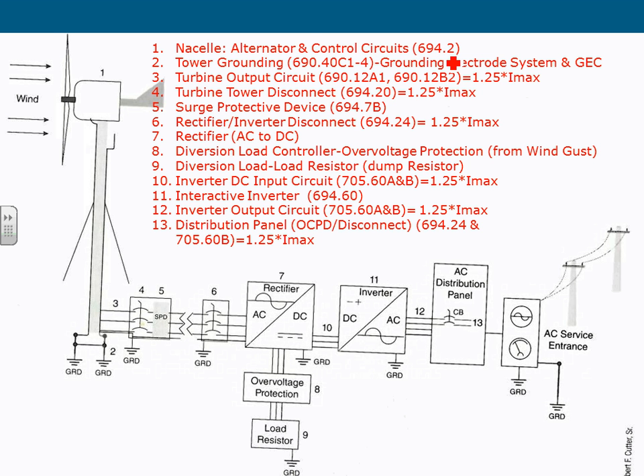Then you go to number three here, they call it the Turbine Output Circuit. Turbine Output Circuit, and I did a couple of calculations. These are all from the NEC code book, not to overwhelm you. I have a couple of slides from that. So when you bring the wires here, typically your three wires coming from the turbine into your disconnect, these need to be sized. You guys are all electrician engineers.